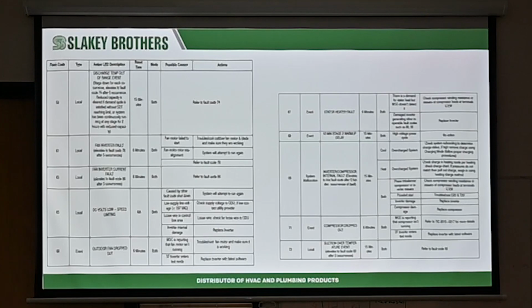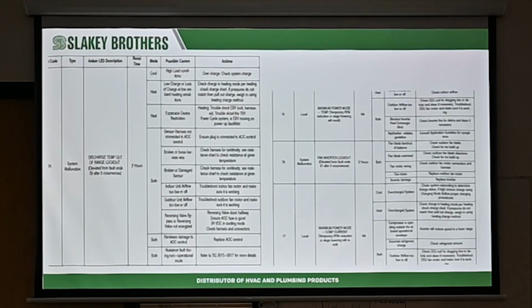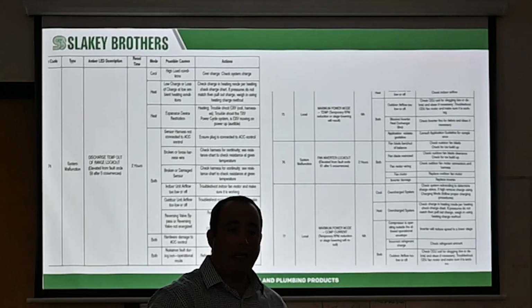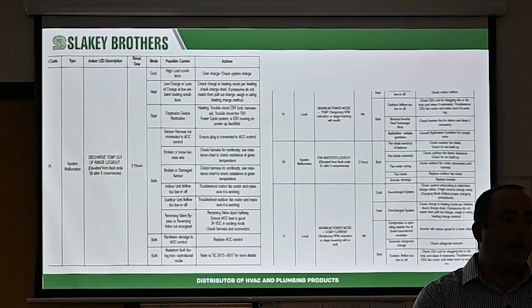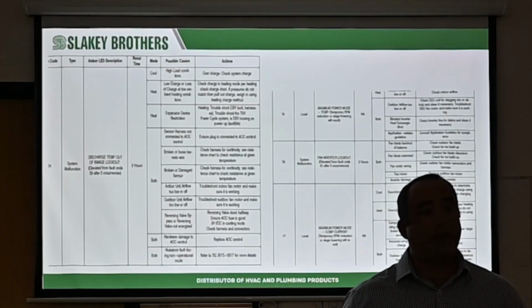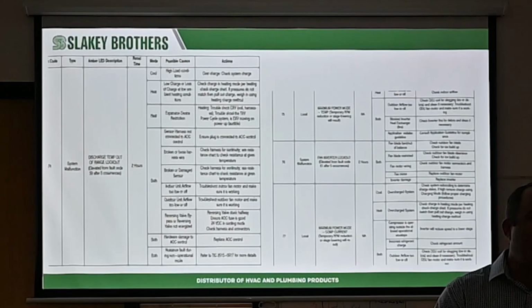The most difficult, whether it's this or the Evolution Extreme, is when you start getting compressor faults or lockouts, that there's something wrong with the inverter board or something wrong with the compressor. In those books, the Evolution Extreme or the 5-stage, you're going to have some simple steps. You're going to check out ohms. Before you say, I'm going to change out the compressor because it doesn't want to start and it's telling me it's got an inverter fault, you check out your compressor. It's got ohm readings that your compressor should ohm out to.